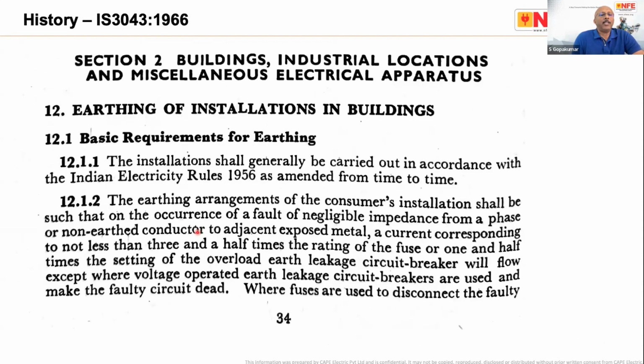Also the explanation, for example, clause number 12, industrial and commercial buildings, basic requirements of earthing. You can see 12.1.2: the earthing arrangement of consumers' installation shall be such that on the occurrence of a fault of negligible impedance from a phase to an earthed conductor or adjacent exposed metal, a current corresponding to not less than 3.5 times the rating of the fuse, or 1.5 times the setting of the overload earth leakage circuit breaker, will flow, except where voltage operated earth leakage circuit breakers are used, and make the faulty circuit dead. So the automatic disconnection of the circuit has been discussed since 1966. It's not a new subject, in fact.